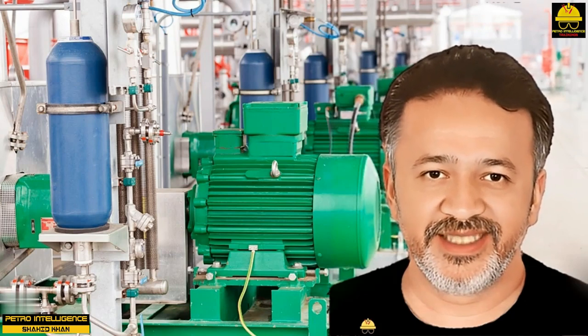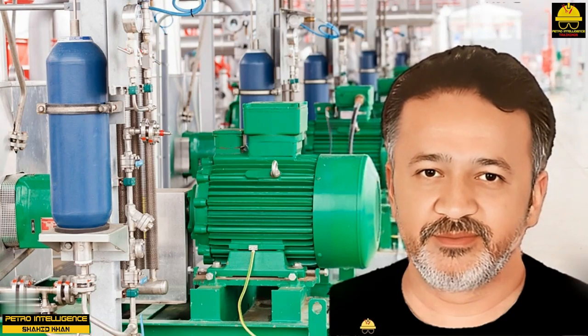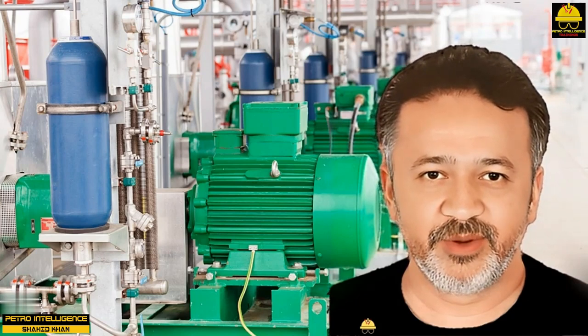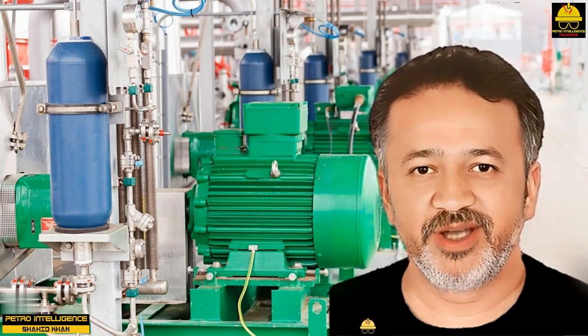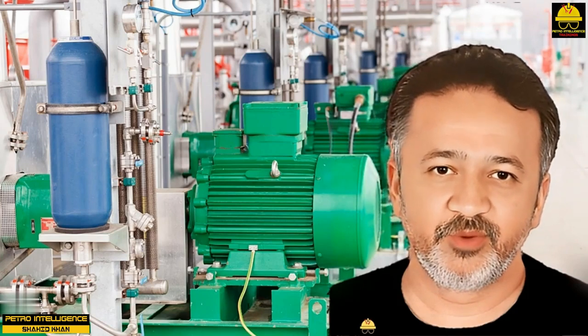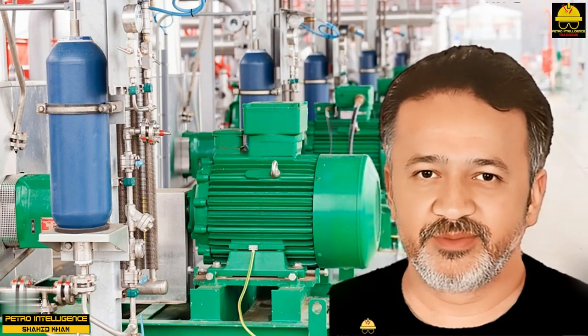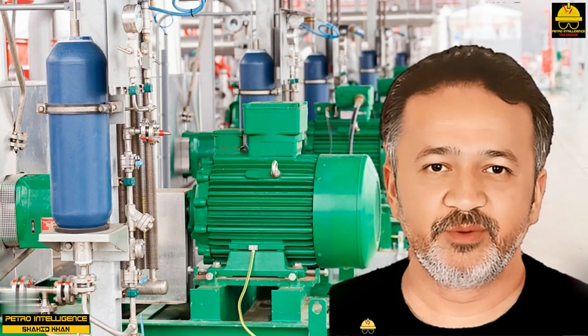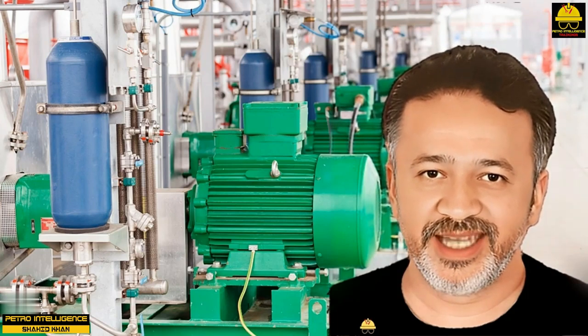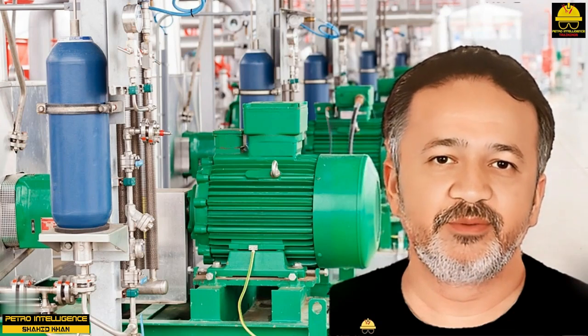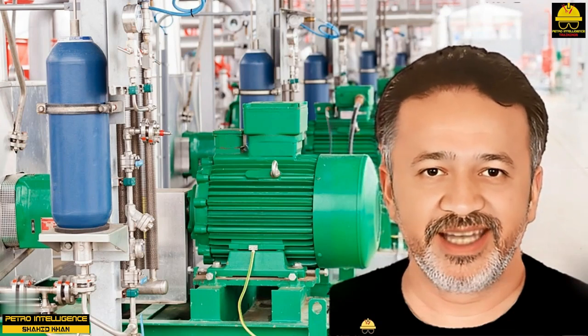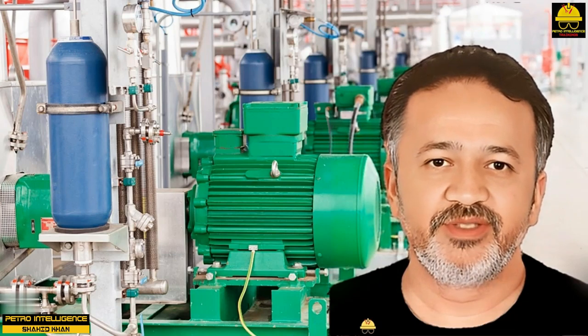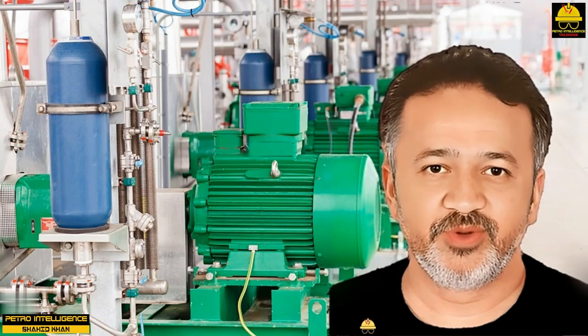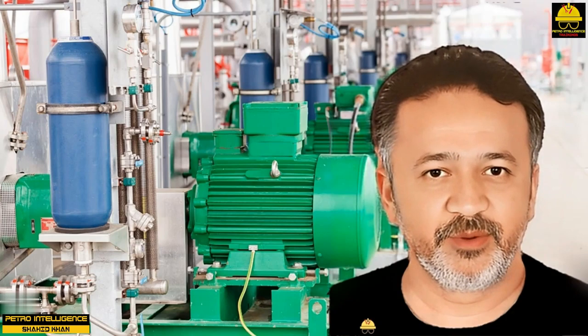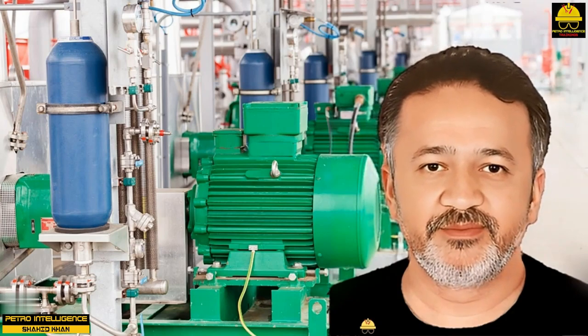Operators easily can identify a pump that is cavitating. The sound of a cavitating pump closely resembles the noise you would hear if steel ball bearings were dumped into a pump suction line. The operator also can expect to see rapid swings in the discharge pressure. Cavitation sends slugs of liquid and vapor through the pump. Each slug has an impact on the internal components of the pump. Serious damage will occur if this problem is not resolved quickly.